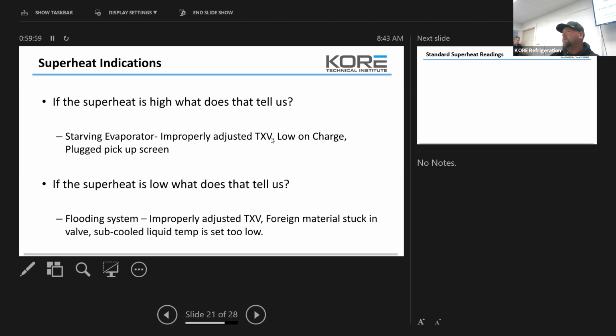as superheat. So we had a lot of issues with the low profile coils in Maverick. It's because everybody was setting the superheats way too high. They actually want you to flood that coil, meaning they want that superheat running at about 4 degrees, which is really low for a beer cooler, but that's where they want it. So we had issues for a long time, a few years back, because everybody was setting them at 12 because it was a cooler. So there is a slide on here that's going to give us general rules of thumb.